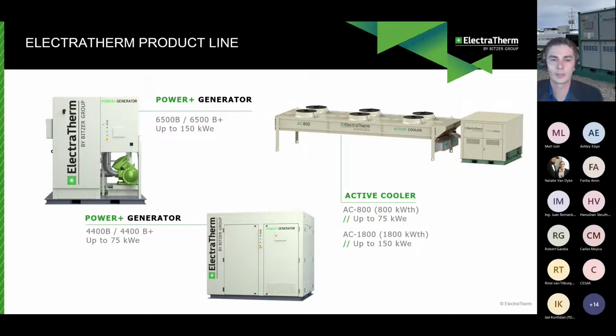As we get into more details on the active cooler, I'll highlight that it is always on cooling. And of course, it's not a one size fits all with regards to heat rejection. I mentioned it gets its name from 800 kilowatts of heat rejection. That's what it utilizes for power production. But if you have an engine that has roughly 1.2 megawatts of thermal energy, then we would be able to reject that as well.